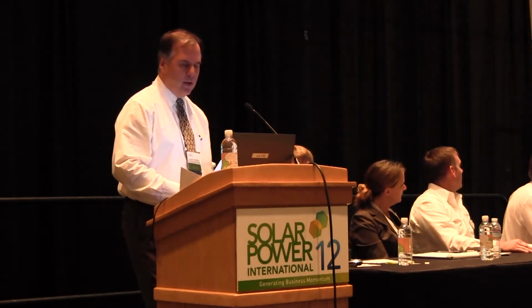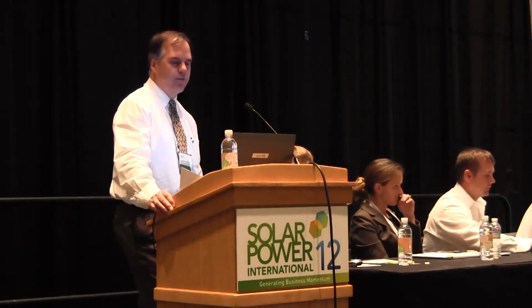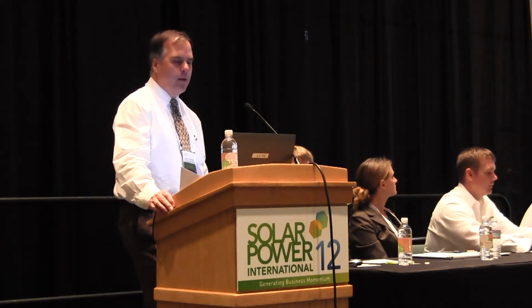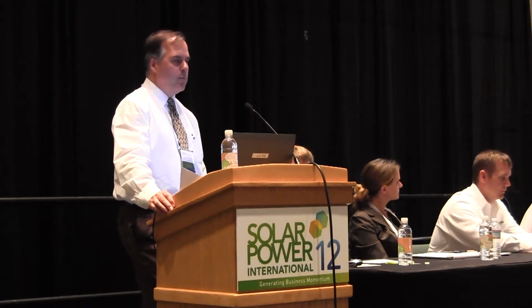So one of the suggestions for modifying the 15% screen, which I'm sure a lot of you have heard about, it's certainly in the FERC docket right now, based on a SEIA petition, to look at the 15% screen. And there's two ways to look at how we could modify that. First, we could, of course, increase the peak load percentage, i.e. go to 25 or 35%, for example. Or probably more appropriately, to look at a percentage of the minimum load. And what's currently in front of the FERC is to establish that threshold based on 100% of minimum load.